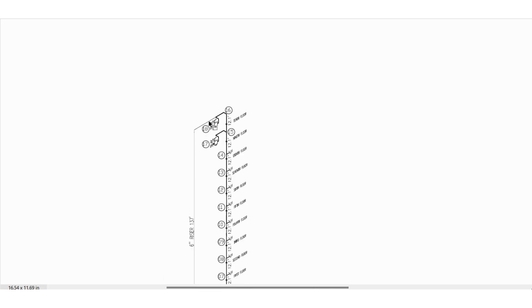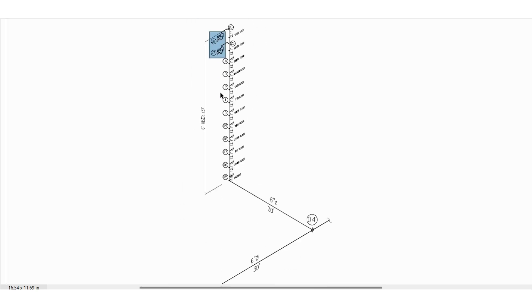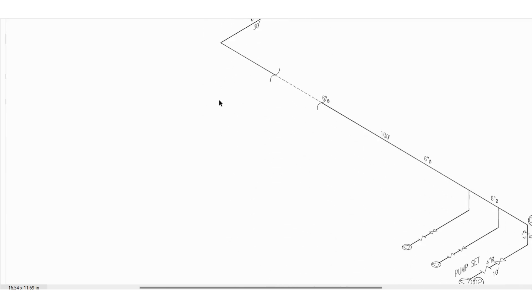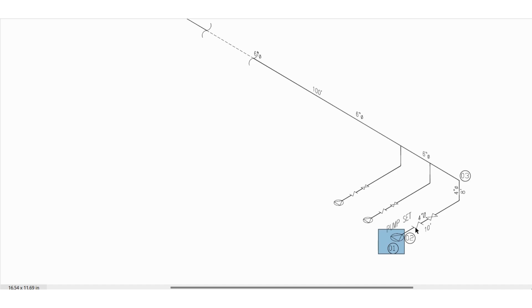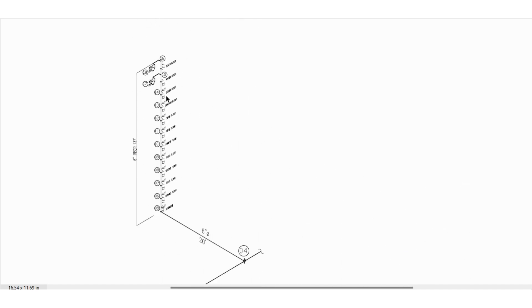There are two things to understand while performing the calculation. From each landing valve we need a flow of 250 GPM. So 250 plus 250 equals 500 GPM. Based on this isometric, we got the demand as 500 GPM. For demand, no need to perform the calculation. But we need to know the pressure required at this particular node so that we will reach our required pressure at the landing valve. As per NFPA 14, we need 100 PSI at the remotest landing valve.